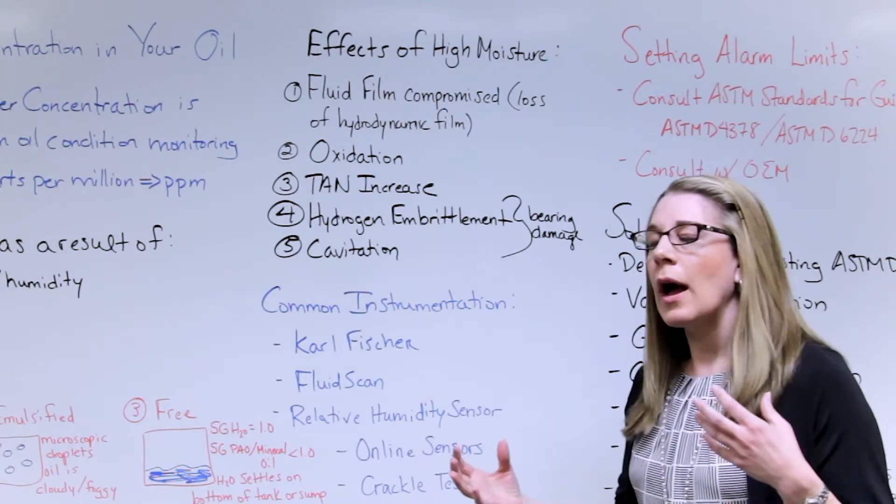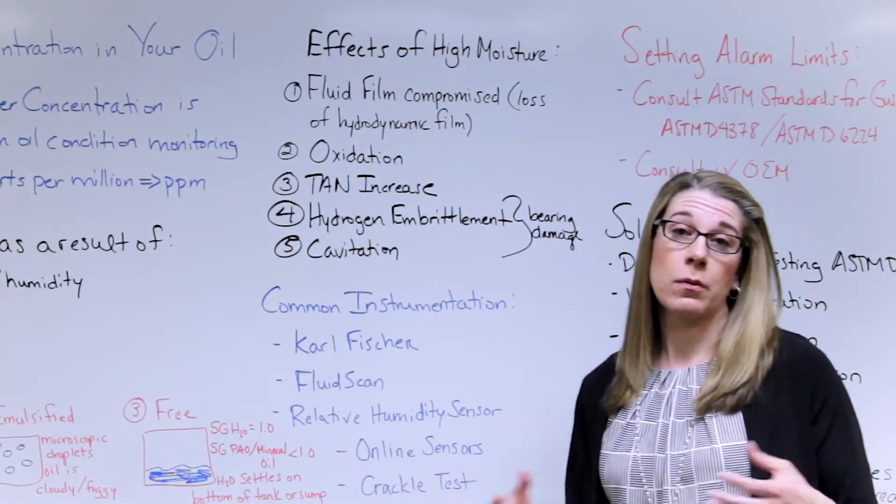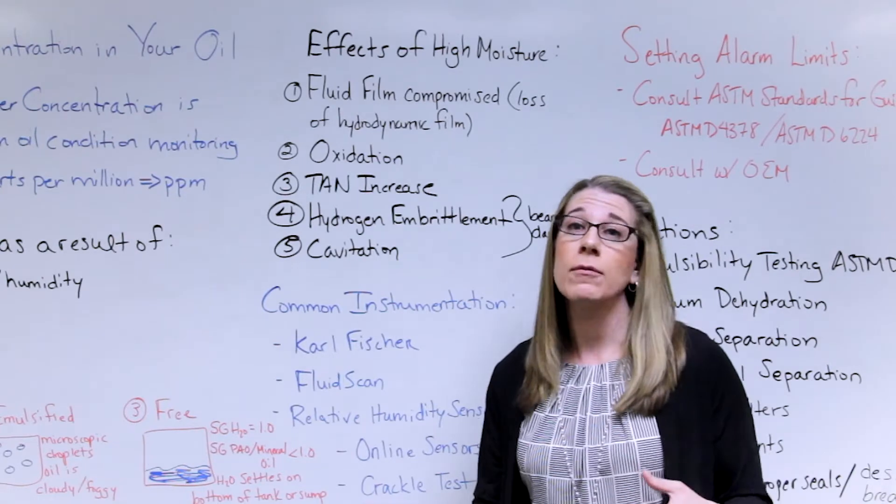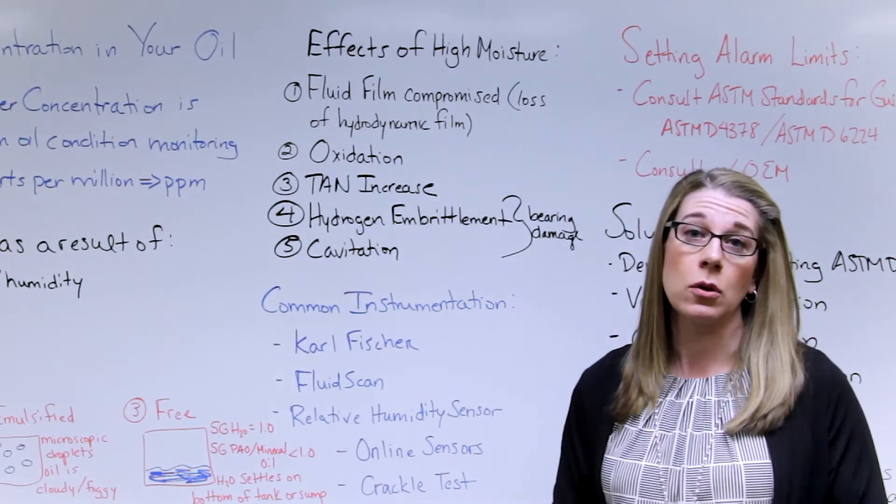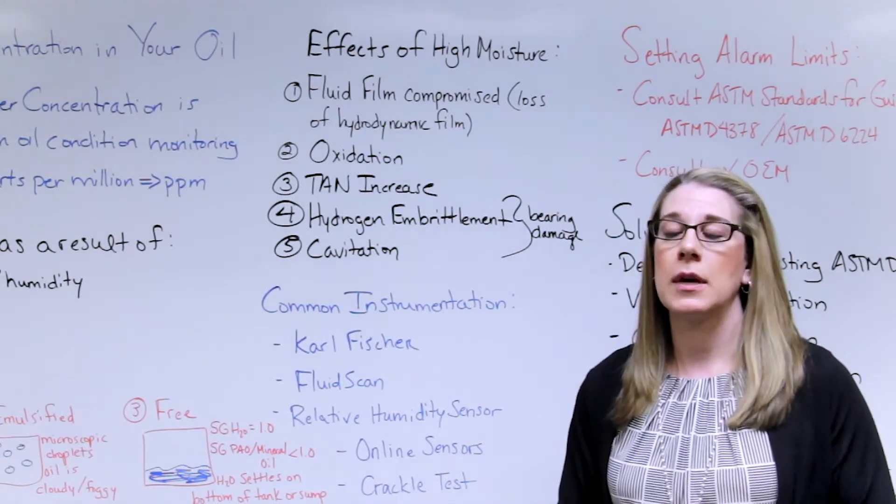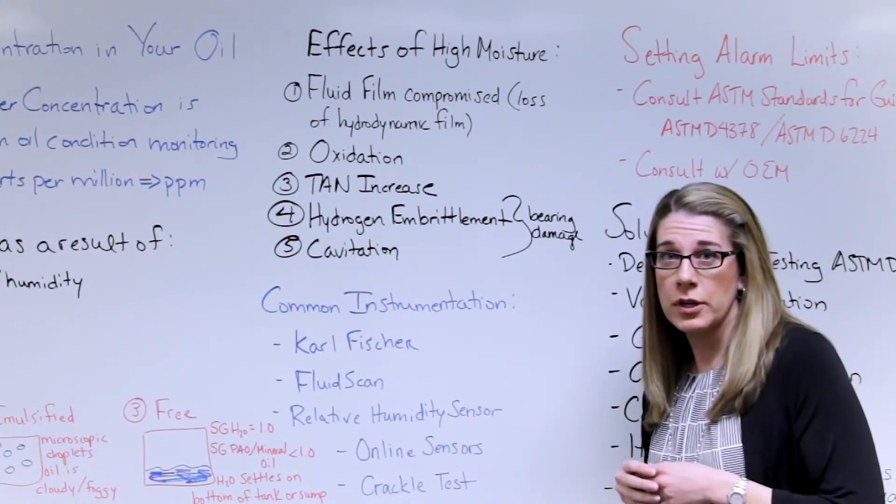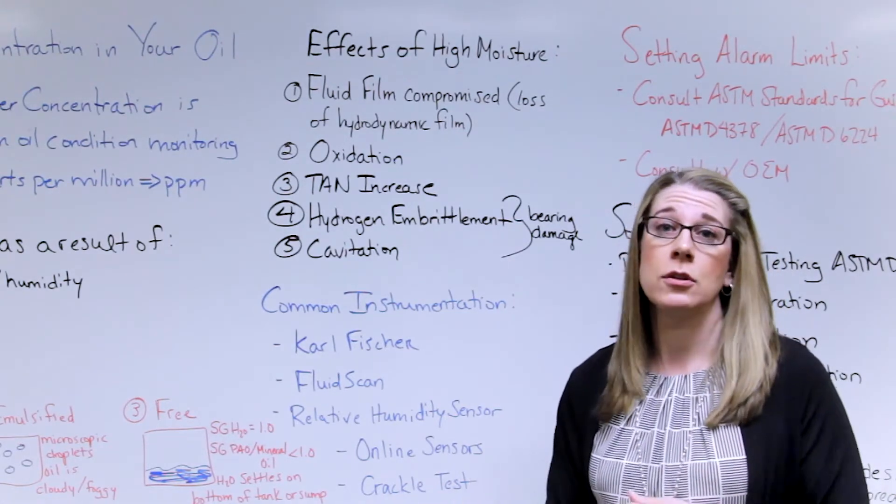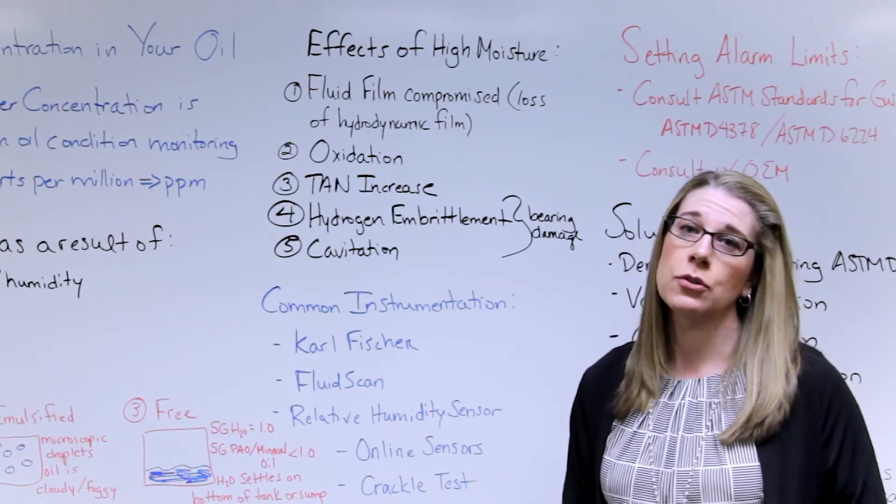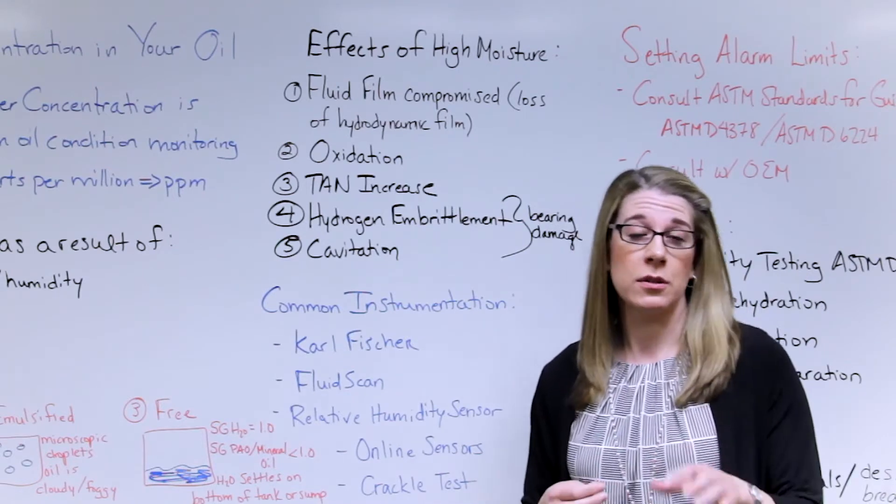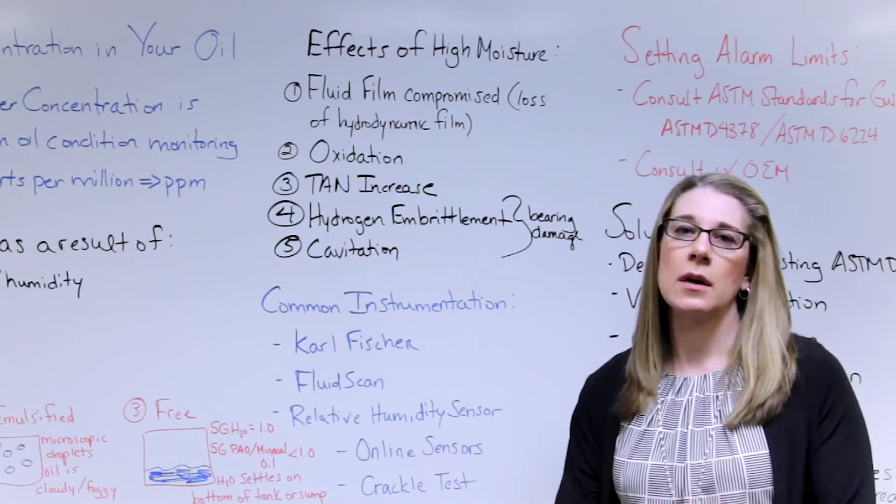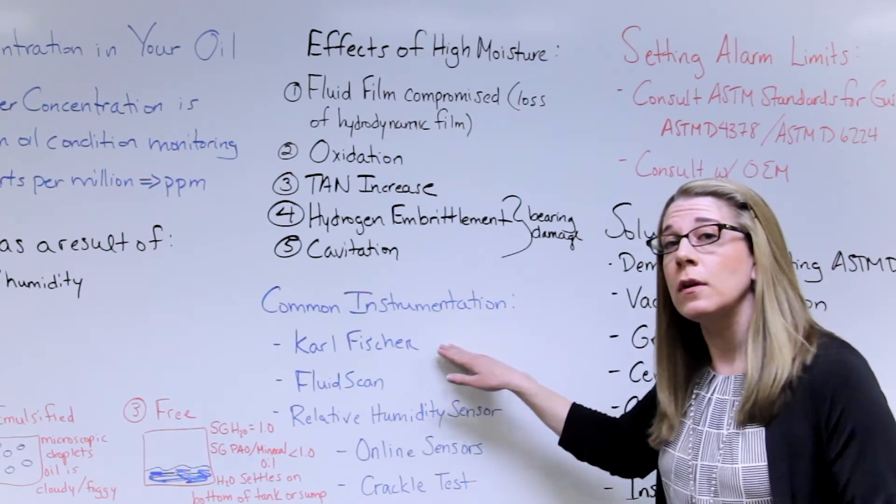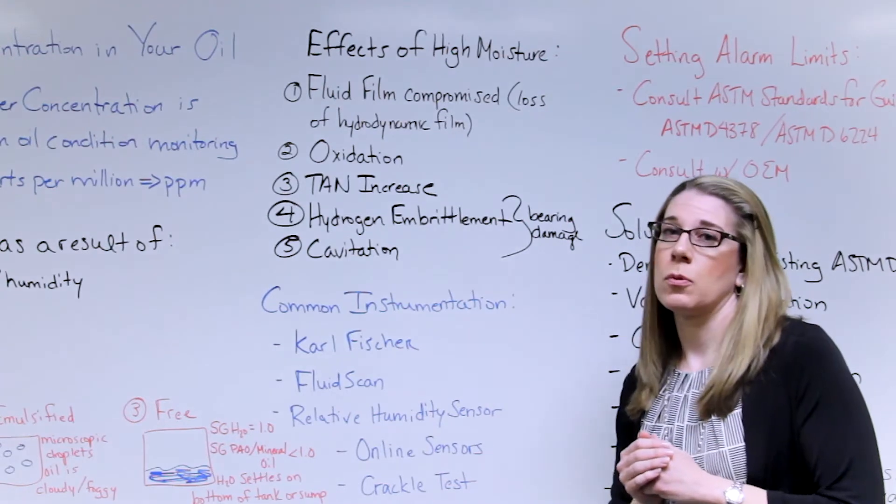How can we go about measuring moisture, and how can we measure it on site? How's it typically been done in a lab environment if you've been outsourcing your oil samples to get it monitored? More than likely they're running a Karl Fischer titration. This is done using iodine to do the titration. You have a generator electrode and a detector electrode. There's a Karl Fischer reagent which is a rather harsh reagent. This is specifically done in a lab environment and is a very precise method that can get down to very low levels of parts per million.